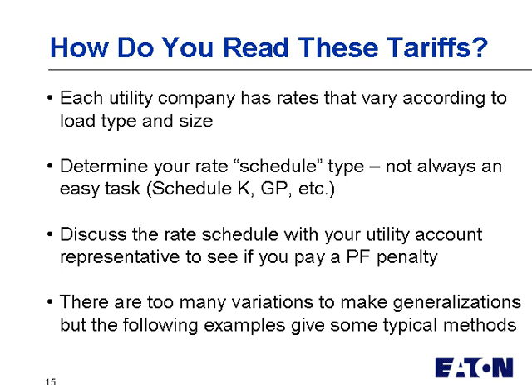How do you read these tariffs? Each utility company has rates that vary according to load type and size. So that means if you're a 1,000 kW customer, you pay a different rate than a typical 100 kW customer. And that's why in our residence we only pay, for example, kilowatt hour charges, and in larger facilities we pay kilowatt demand charges as well.